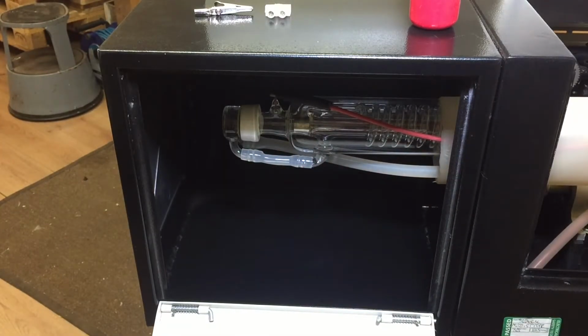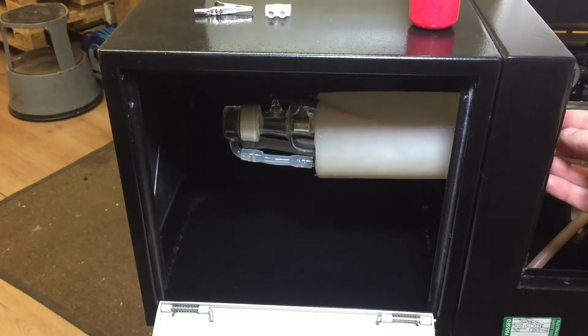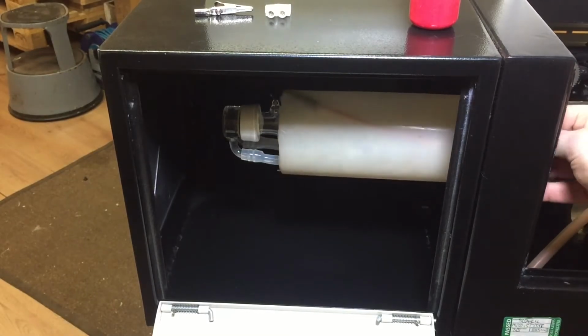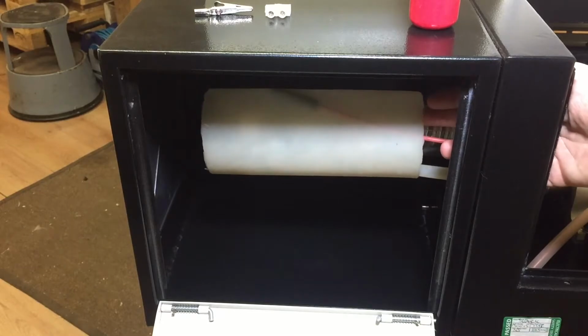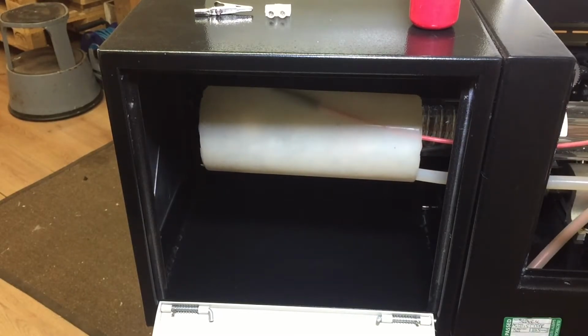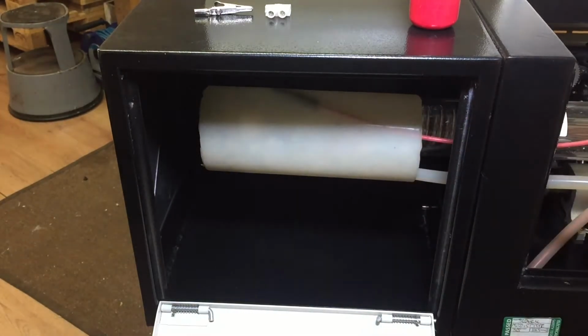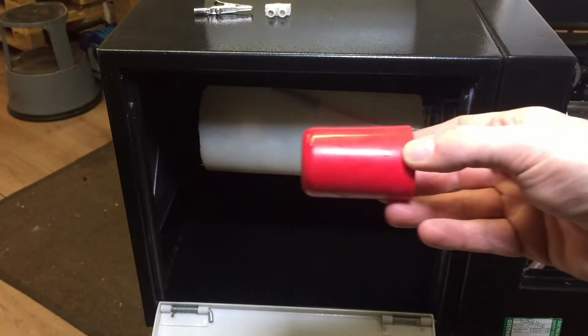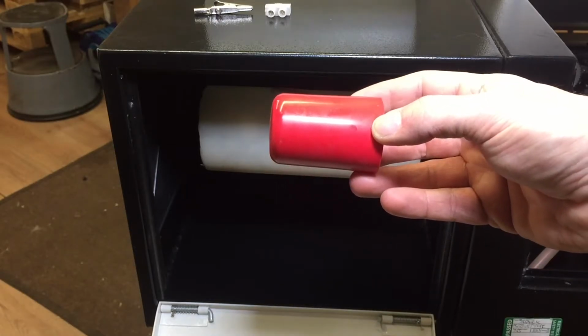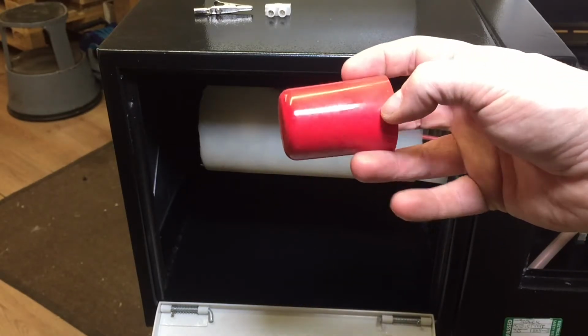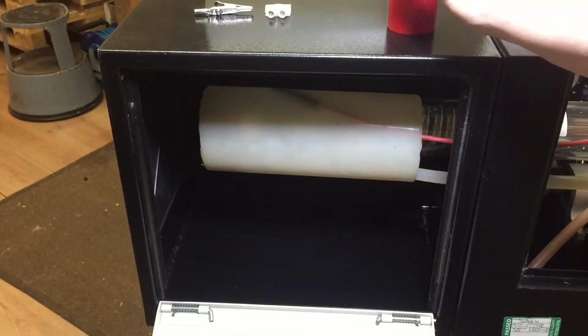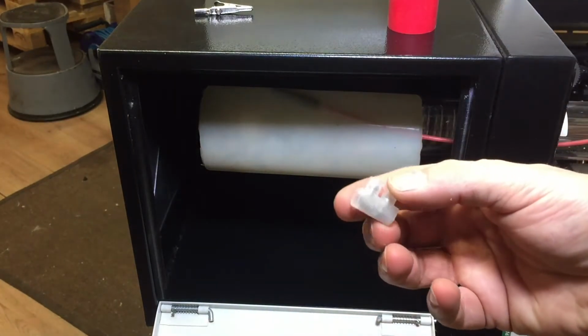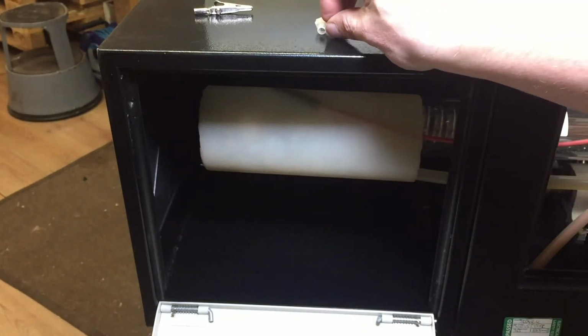The high voltage wire on this particular laser cutter is attached using a brass ferrule, and insulation is provided by this rubber sock which fits over the end, preventing any arcing between this high voltage part and the case of the machine. Sometimes you will find that a rubber end is placed over the connection for the red wire, the high voltage wire, and on some occasions I've even seen a chock block used.